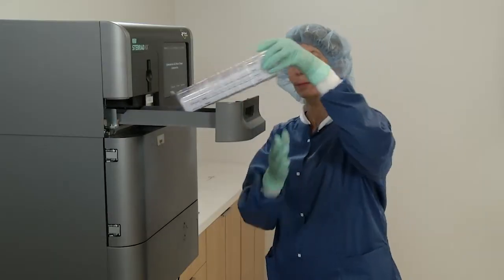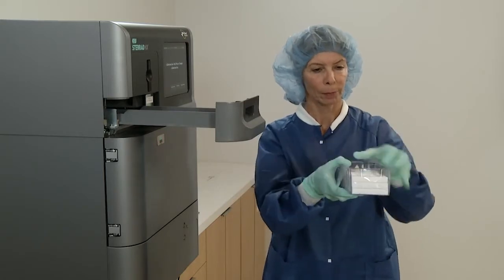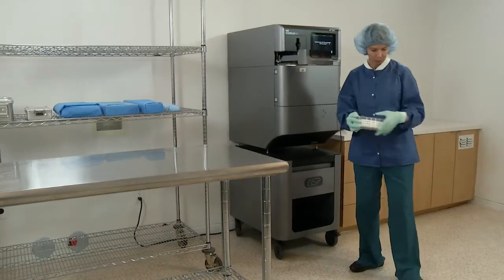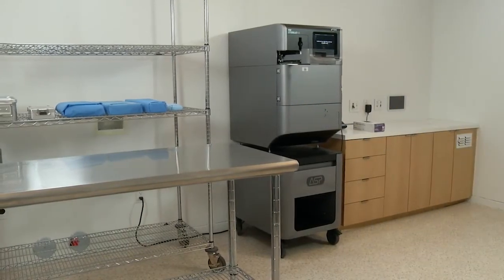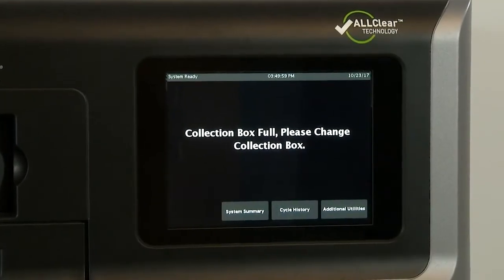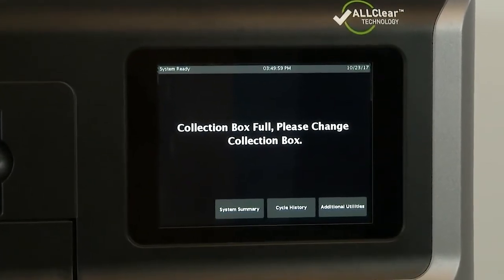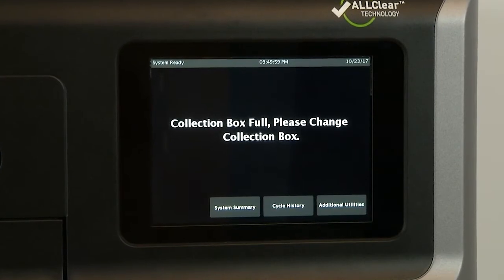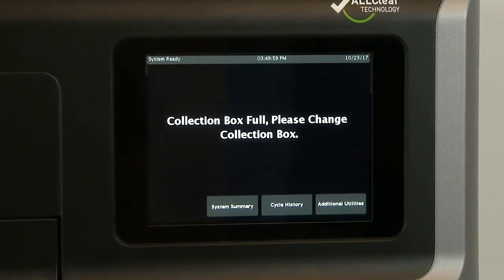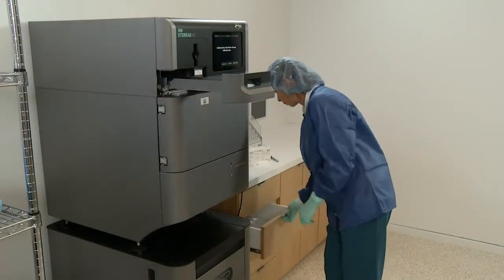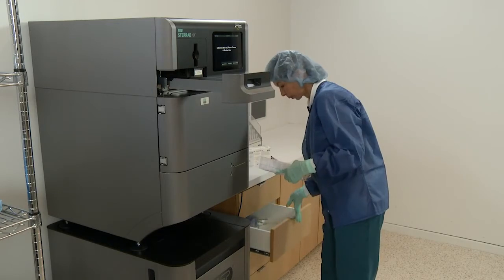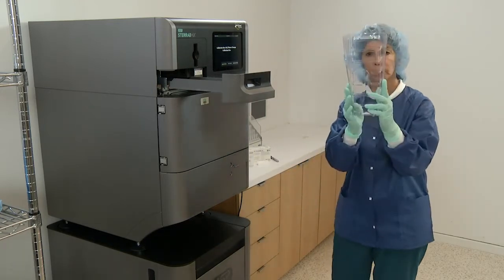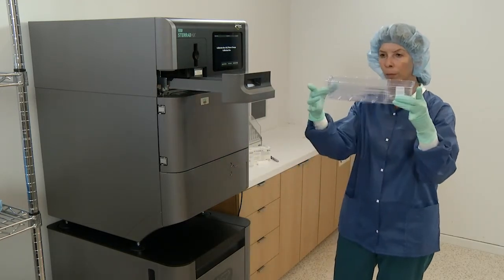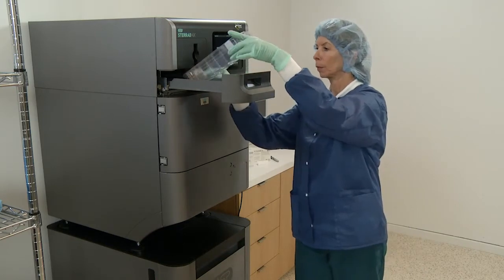When the cassette disposal box contains 3 cassettes, it is full, and you must dispose of the full cassette disposal box. The screen displays a message instructing you which actions to take next. For safety reasons, you must use the cassette disposal box to dispose of cassettes. Never reuse a cassette disposal box. Wearing gloves, once a cassette disposal box has been removed from the drawer, a new cassette disposal box must be assembled and inserted in the drawer.